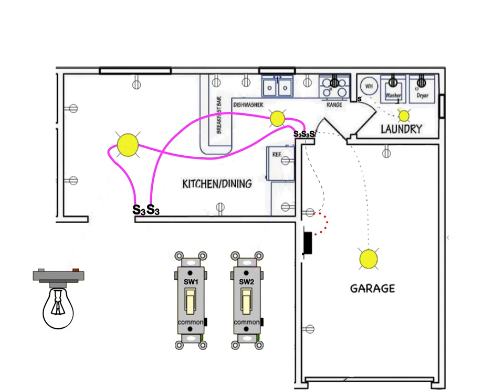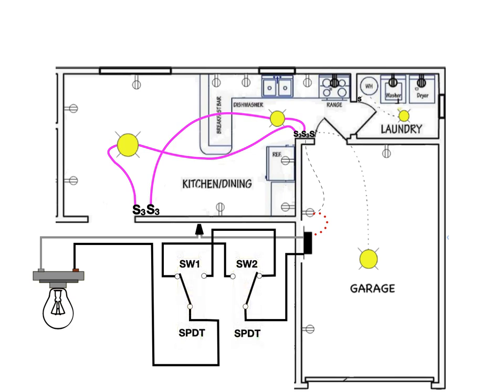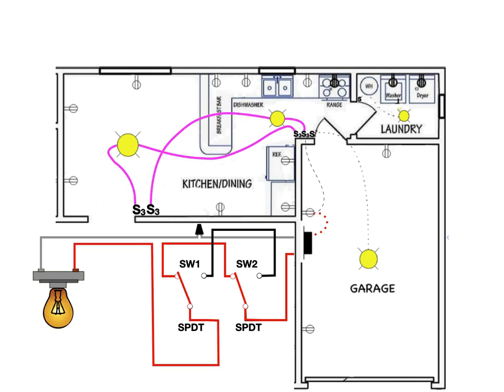Switch number two is being fed with power from a hot wire connected to its common terminal. Switch number one's common terminal is connected to the hot terminal of the light. Neutral is connected to the neutral terminal of the light. The traveler terminals of the switches are connected in parallel. A three-way switch is a single-pole, double-throw type of switch. I am going to color-code the wires red that are electrically hot, or at 120 volts, for various positions of the switches. With the switches in this position, the light is off. Toggling switch number one carries 120 volts all the way to the light — the light is now on. When switch number two is toggled, the hot circuit to the light is interrupted and the light is off again. Toggling switch number one again completes the circuit to the light.